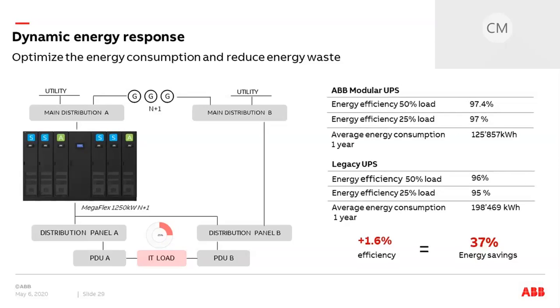Now, same topology, but the IT load is varying between 50% during the day and less than 30% during some hours at night. On the right side, we have the UPS efficiencies for the 50%, 20% and 25% load, with a difference of up to 2% when the load is under low conditions. The variation of the load over a year will represent a difference in the efficiency of 1.6% for ABB modular UPS, increasing the energy savings from 35% to 37%.